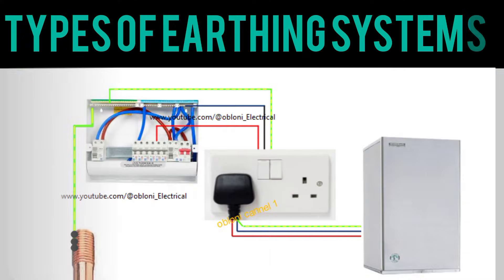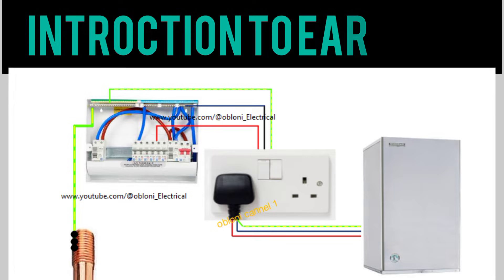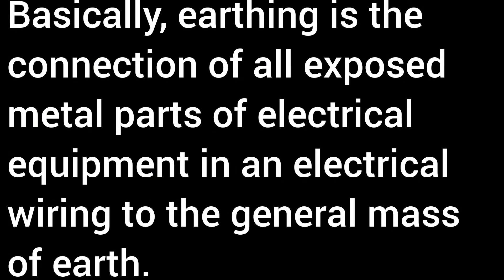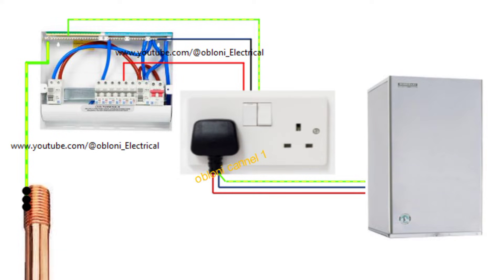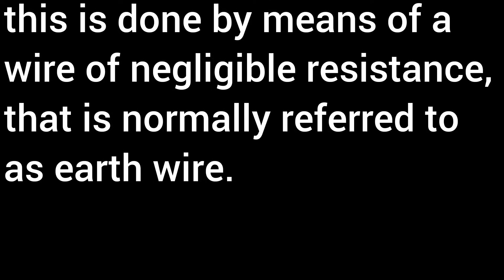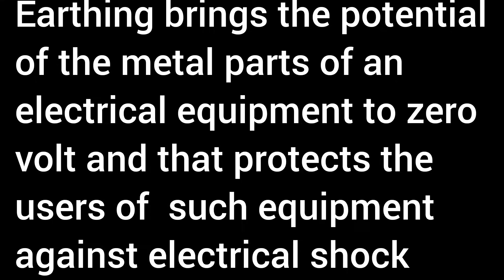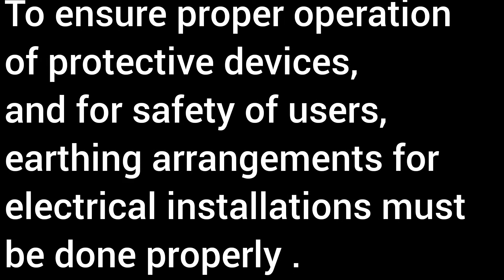Types of earthing systems. Earthing is the connection of all exposed metal parts of electrical equipment in an electrical wiring to the general mass of earth. This is done by means of a wire of negligible resistance, normally referred to as the earth wire. Earthing brings the potential of the metal parts of an electrical equipment to zero volts, and that protects the users of such equipment against electrical shock. To ensure proper operation of protective devices and for safety of users, earthing arrangements for electrical installations must be done properly.